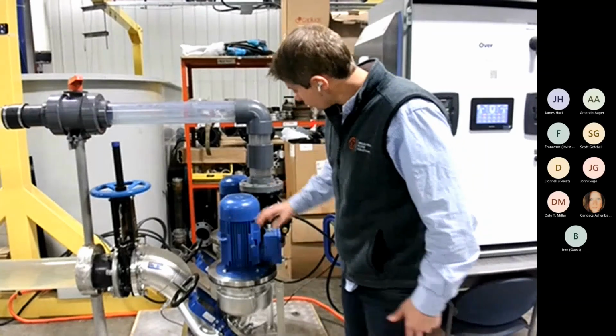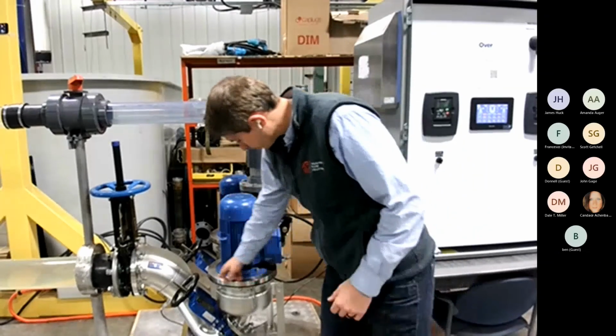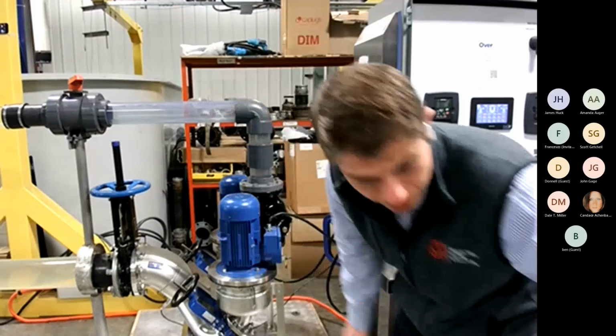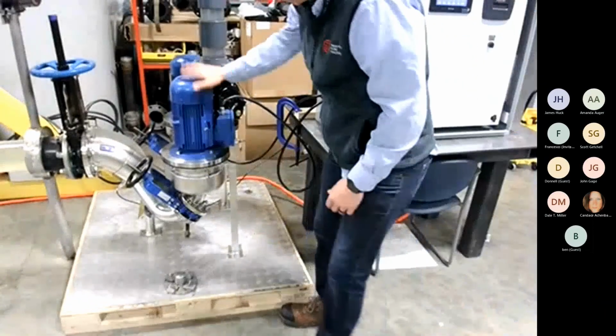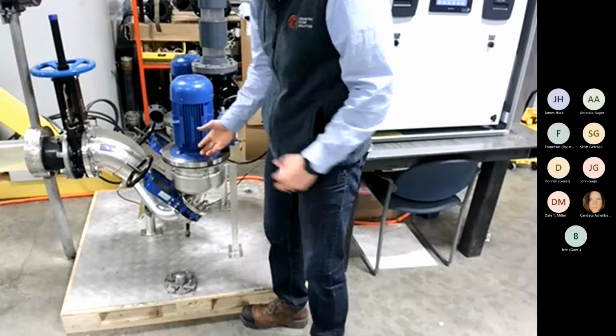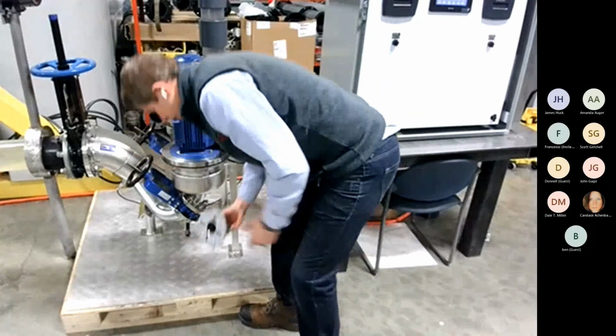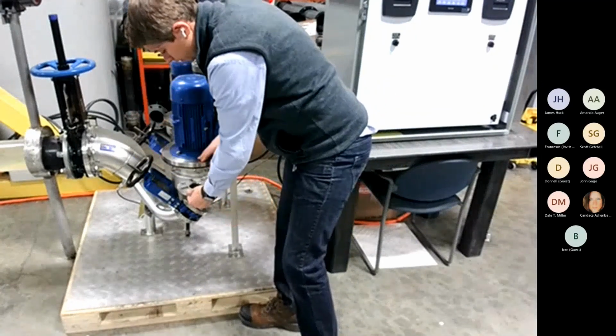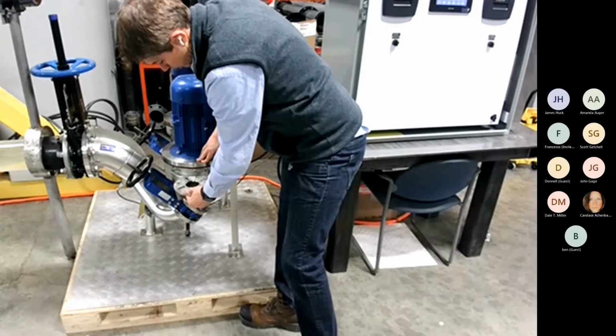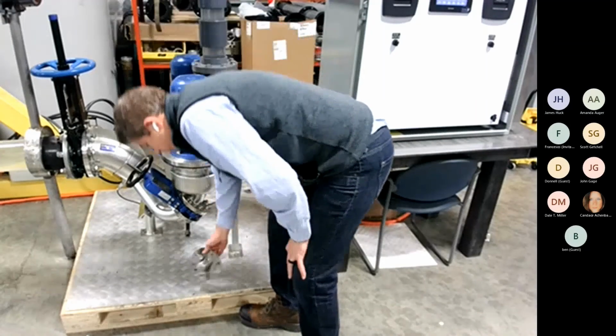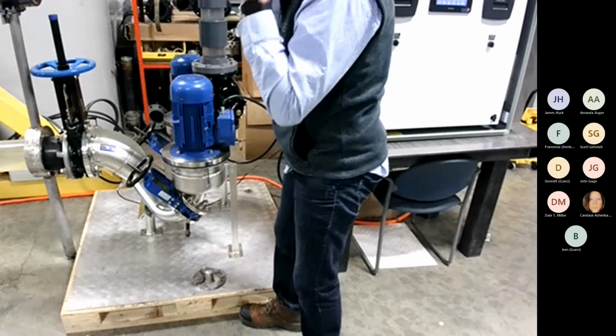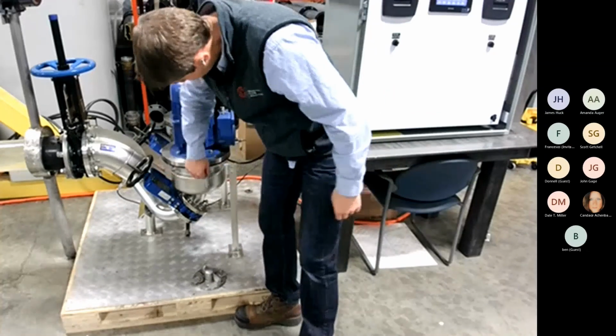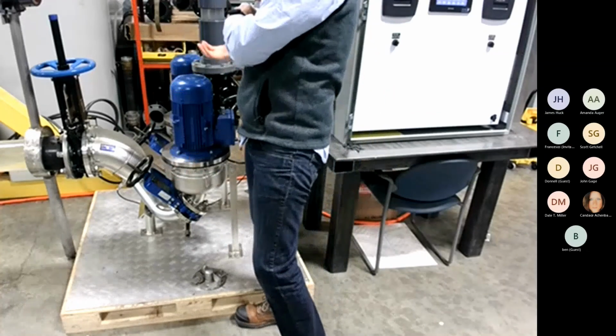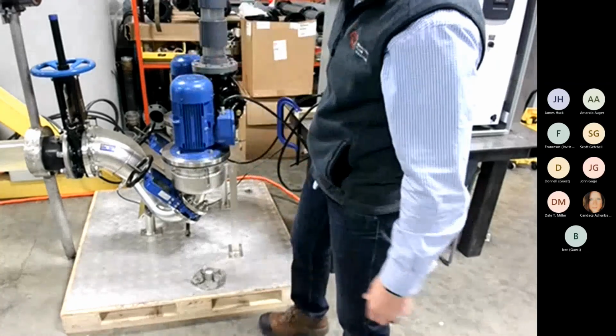This motor assembly sits on this motor mounting plate, and the impeller is actually close coupled to the shaft right on the underside of the impeller. So when you need to remove anything, you just remove these 8 bolts along the bottom, and this whole assembly comes off the top, and now everything is there to be maintained.